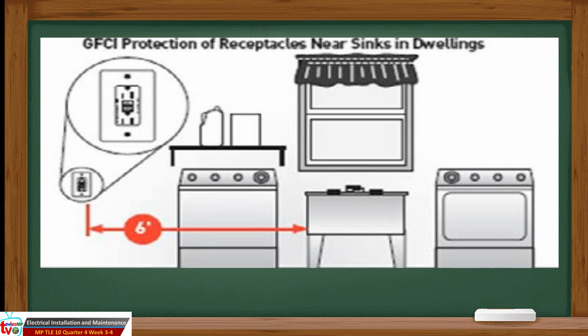GFCI protection is required for receptacles installed within 6 feet of laundry sinks, wet bar sinks, and utility sinks in dwelling units. This requirement previously applied only to receptacles installed in countertop surfaces within 6 feet of a wet bar sink. See Figure 1 for GFCI protection of the receptacle near a sink in a dwelling.